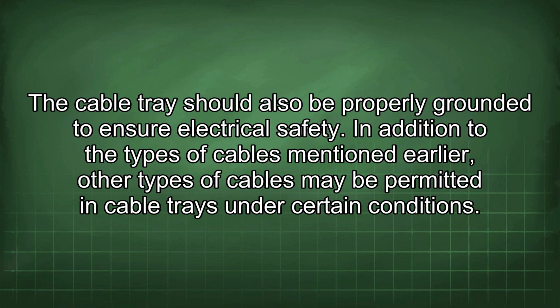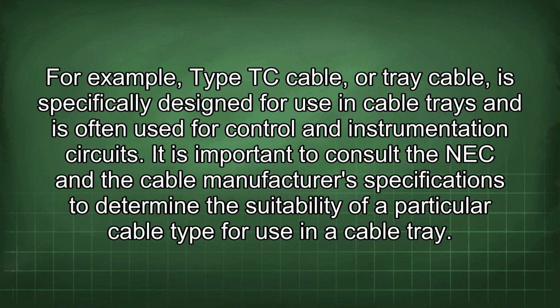In addition to the types of cables mentioned earlier, other types of cables may be permitted in cable trays under certain conditions. For example, Type TC cable or tray cable is specifically designed for use in cable trays and is often used for control and instrumentation circuits. It is important to consult the NEC and the cable manufacturer's specifications to determine the suitability of a particular cable type for use in a cable tray.